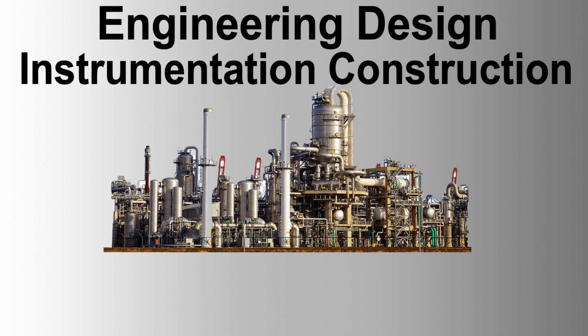The manifold block, which forms part of the impulse line arrangement, shall be bolted to a mounting plate. Mounting of the manifold shall be by means of a 50 mm pipe clamped to the instrument stand. Transmitters shall be supported by the manifold. Selection of the type of mounting plate depends upon the various components required. L-shape, when a sunshade is required. When a junction box is required, in combination with a requirement for a protective housing for transmitter.